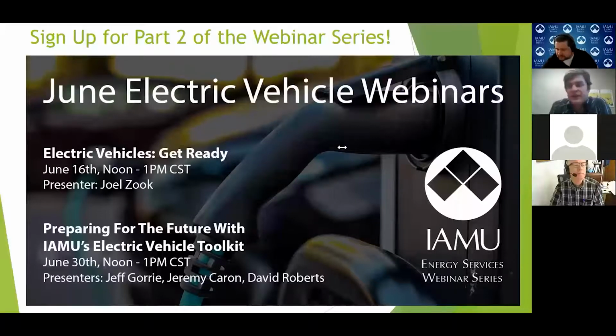I think anytime. In my opinion, it will respond to market conditions. If it's a project that a utility is figuring out how to put in and finance themselves, it makes a lot of sense to have some batteries next to some EV chargers to manage whatever portion of your distribution grid that you've got it on. If it's a third party that's putting this in, what is the balance between your energy cost and your demand cost? If they're getting killed on a demand cost, they're going to put some storage in.